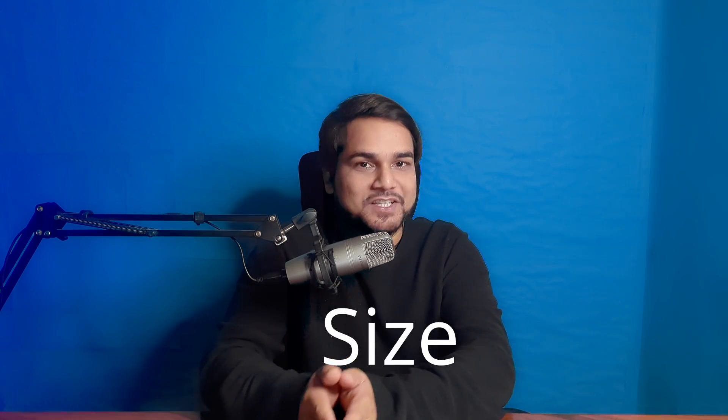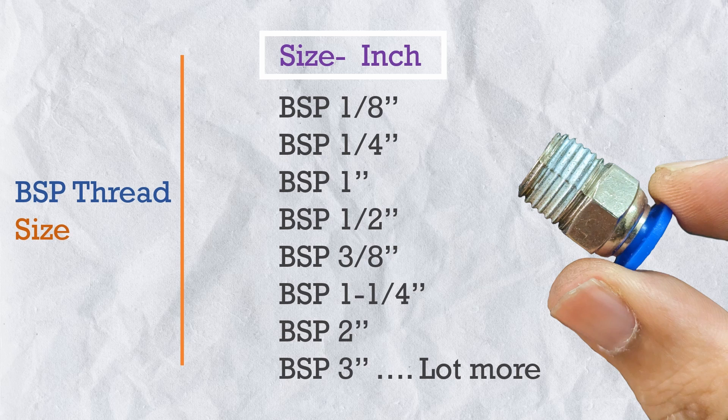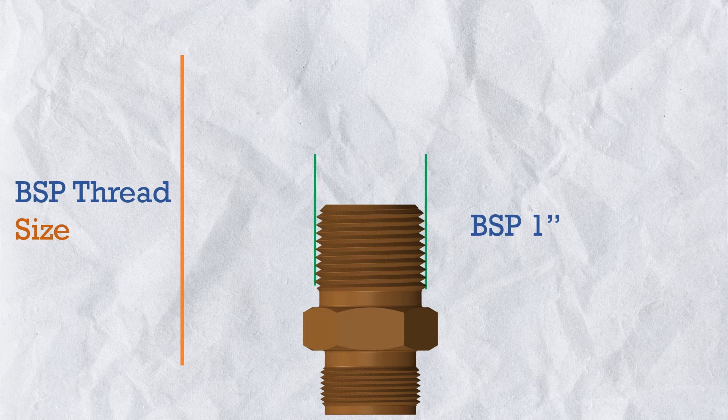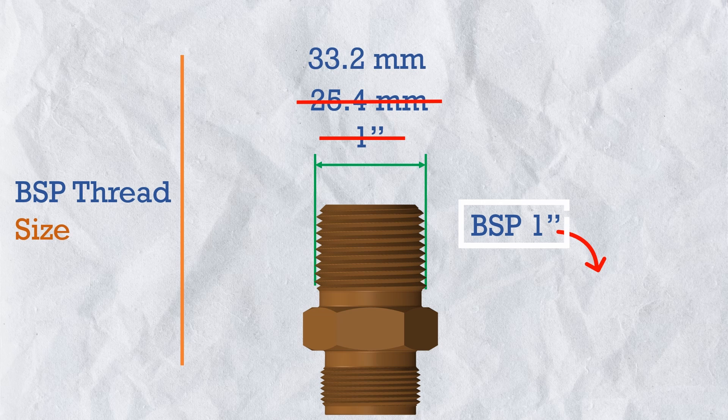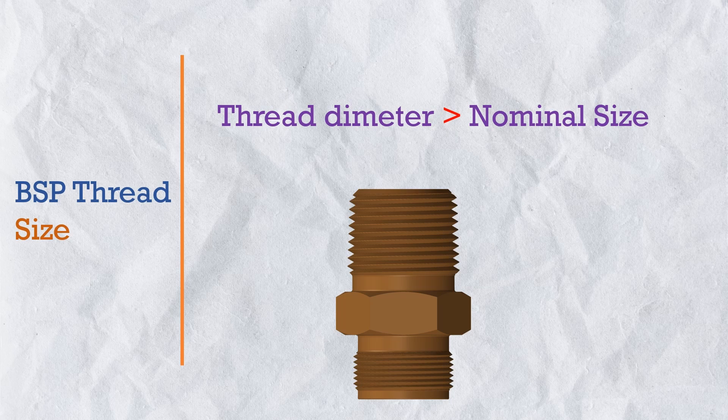The first thing is the size of BSP thread. We define BSP thread sizes in inches like 1/8 inch, 1/4 inch, 1 inch, or 1/2 inch. But these inches are not the diameter of the thread. For example, a 1 inch BSP thread doesn't mean the thread diameter is 1 inch or 25.4 mm — it's actually 33.2 mm. This is just a nominal size: a reference number, not a physical dimension. In BSP thread, the thread diameter is always larger than the nominal size, and this nominal sizing in inches comes from historical legacy.